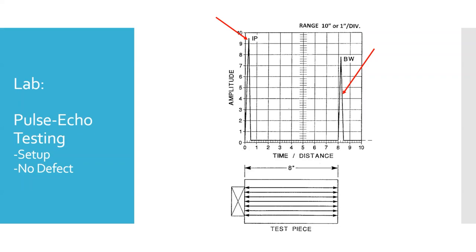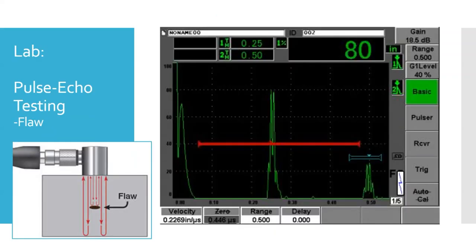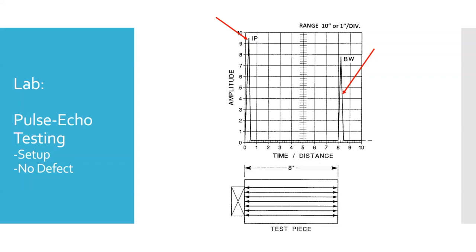The tester is saying, okay, how long is that sound pulse taking? It's going to multiply it by whatever speed of sound you program in to give you your distance. What's the term for data entry when you're referring to data? Anyone ever heard that? Crap in, crap out? When you're dealing with a computer, it's only as good as what you put into it, only as good as the person operating it. You put the wrong speed of sound in, you're going to get the wrong distance out the other end. So we have to calibrate that.